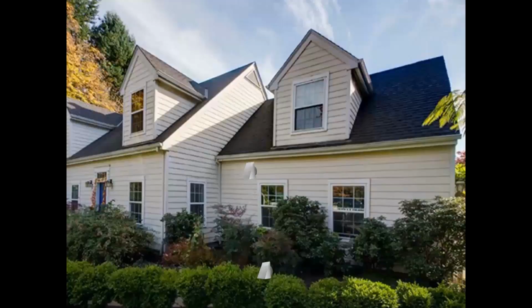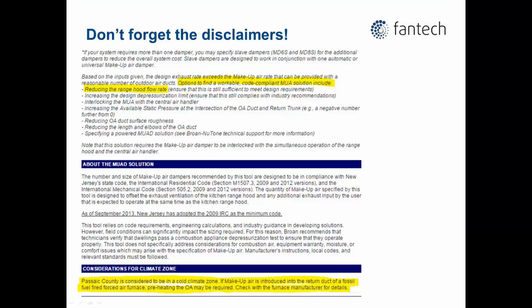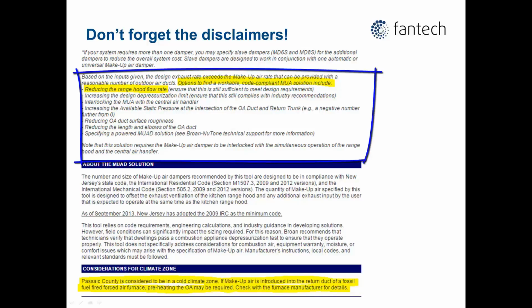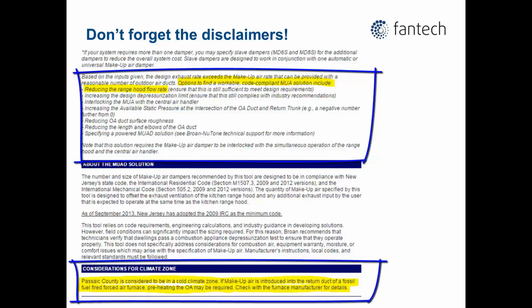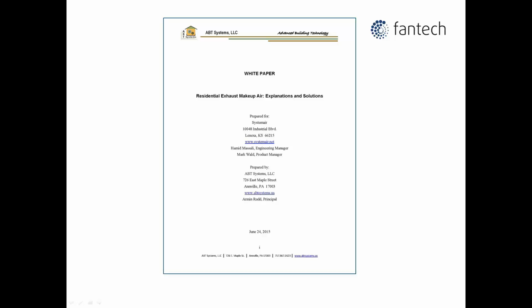Do you really want your home to look like this? Here they tell you that with all those holes, the makeup air is still insufficient for the hood exhaust, and gives some options, which includes downsizing the hood fan. And don't forget, if the air temperature into the return air of the furnace is below the manufacturer's recommendations, normally around 53 degrees Fahrenheit, the warranty on the furnace may be void. In fact, an independent white paper on residential makeup air points out the pitfalls and serious limitations of natural makeup air.